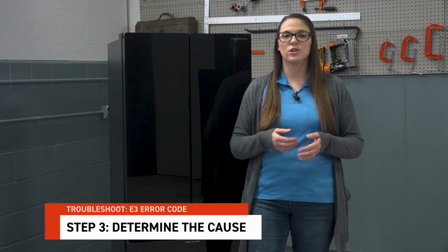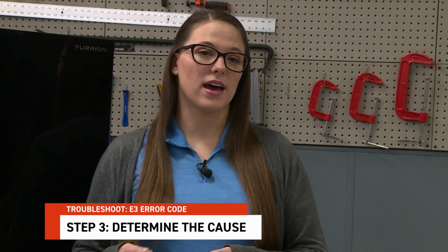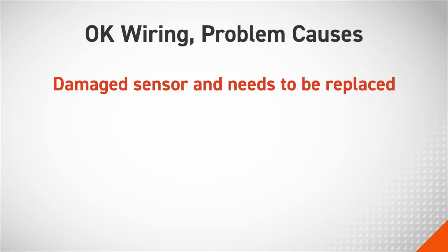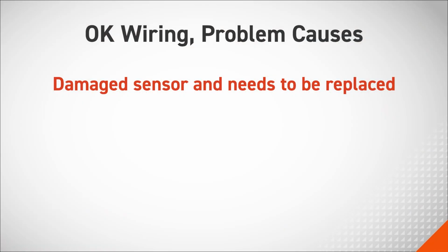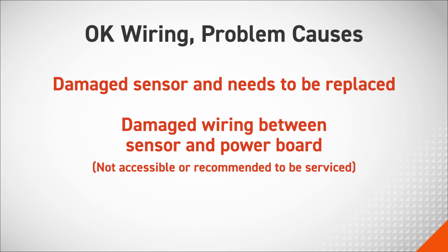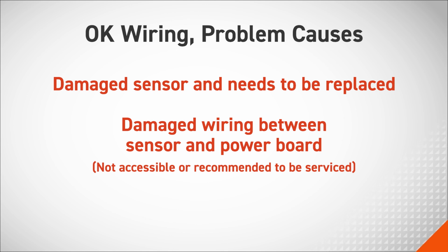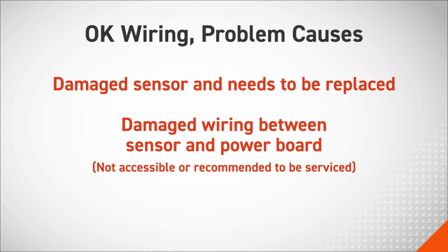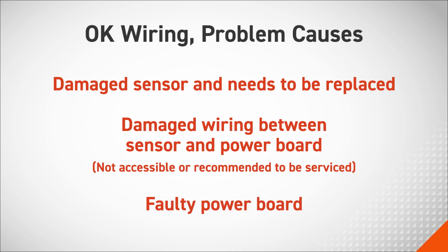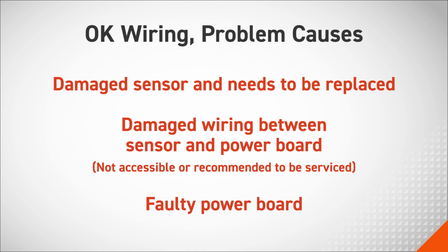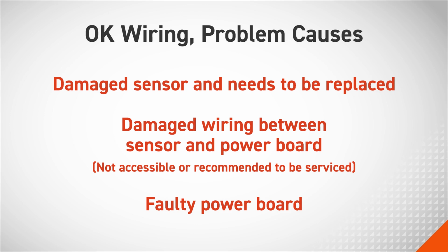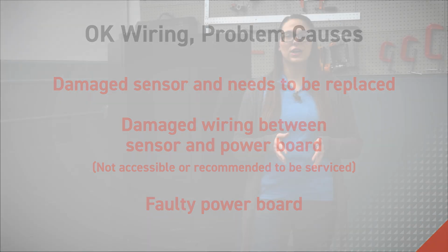Step 3. Determine the cause. If the wiring looks fine, the problem could be one of three things. The sensor is damaged and needs to be replaced. The wiring between the sensor and the power board is damaged, which isn't accessible or recommended to be serviced. Or the power board is faulty, resulting in a false error code and the power board needing to be replaced. To narrow it down, test the sensor.